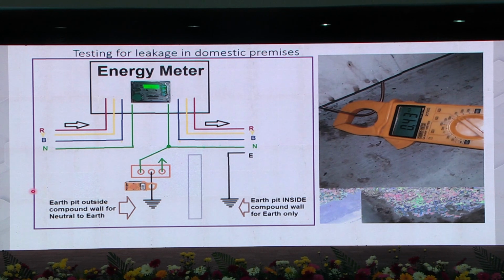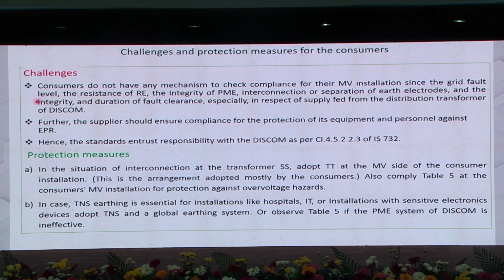So, if you connect without knowing the condition of the distribution transformer and the supplier's or your own transformer, it is very tough to go into the connection. So, the possibility of mitigation is two things. One, the consumer does not have any mechanism to check compliance, because the earth potential rise is dependent upon the fault current as well as the distribution transformer's earth electrode resistance. You don't know what the fault current is, or what earth resistance value is maintained by the supplier. And that's why IS clause 4.5.2.2.3 insists that the supplier, the distribution company, is responsible to maintain it, but practically it doesn't happen.